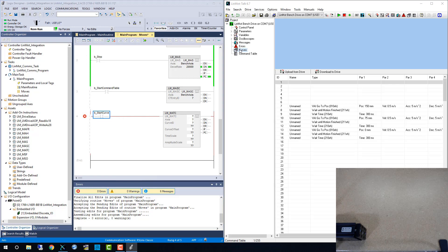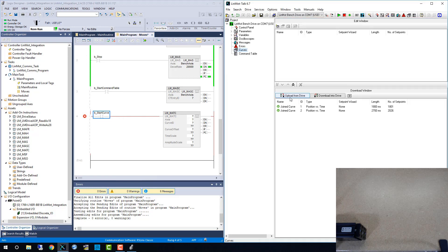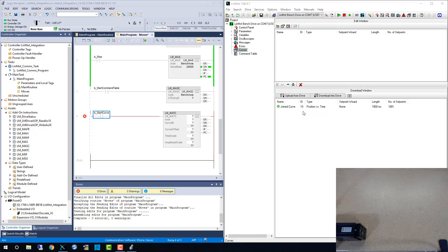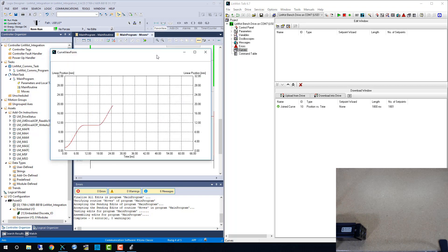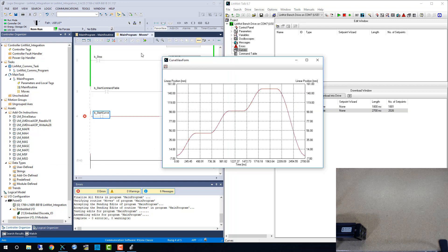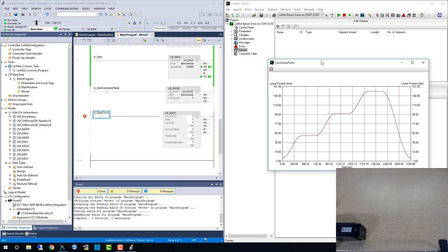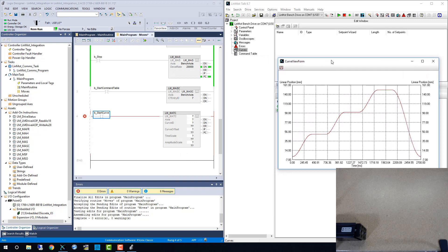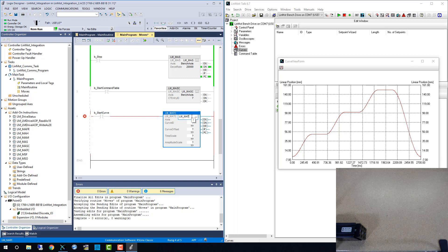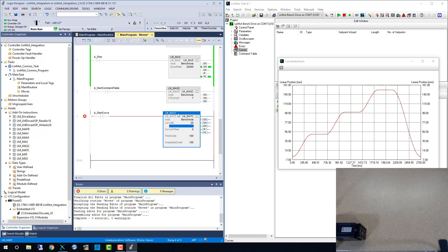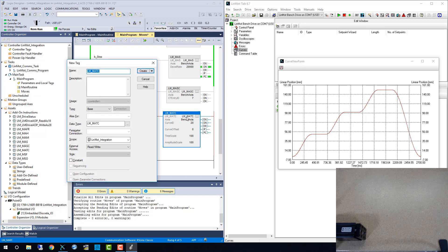Next up we have the LMMATC, or run time curve. Here I'm pulling up the curve as it's stored in the LinMot drive. In this instance we make three short moves and then a quick retract. The values we add to this AOI are the curve ID within LinMotTalk, the offset in millimeters, and amplitude and time scale as a percentage.